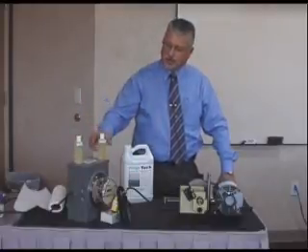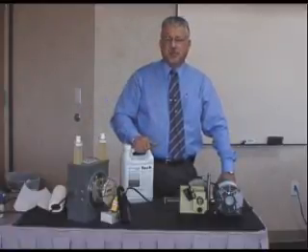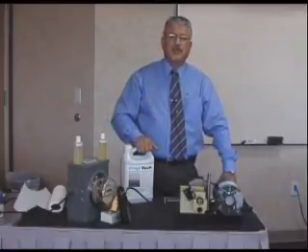What I'd like to do is demonstrate it for you. I'm going to compare Suniso 3GS, which is the industrial standard lubricant used in air conditioning systems in the United States, and then I'm going to add Frigitec to it. Color-wise they look virtually the same. Frigitec is an additive — you add it at five percent by volume on regular AC systems, and about eight percent on ammonia systems. It does not replace the standard oil; you add it to it, and it can be mixed with any type of oil, whether mineral or synthetic, and works with ammonia or Freon systems, even ice arenas with brine systems.